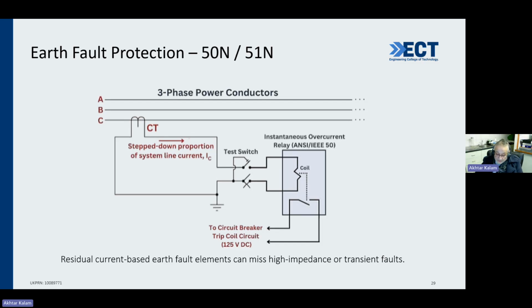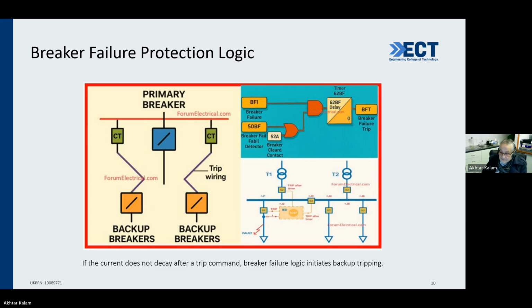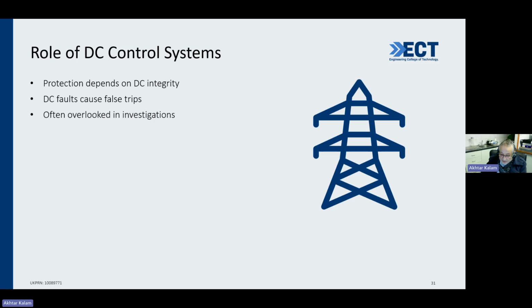Then I look at a third device. My third device is also an earth fault protection, and this one also does not operate for short duration or distorted current. All three that I've talked about do not operate for short duration or distorted current. Although there are a lot of functions in there, it does not operate. And by the way, it costs anything between $8,000 and $12,000 to buy any of this equipment. Nothing is cheap, my friend.